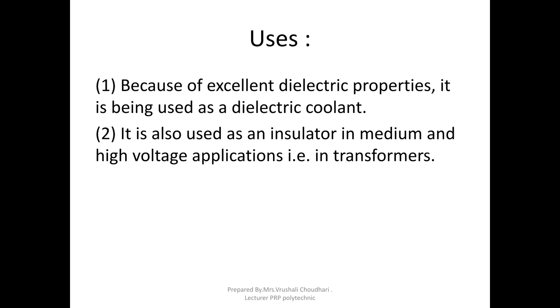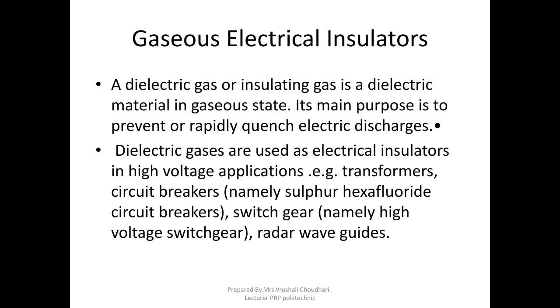Gaseous electrical insulator. Gas or air is a bad electrical conductor. Dry air is an insulator. But in the presence of moisture, the conductivity of air increases. This is also called ionization. Therefore, we cannot use normal air as an insulator in electrical appliances. A dielectric gas or insulating gas is a dielectric material in a gaseous state. The main purpose is to prevent electric discharge. Dielectric gases are used as electrical insulators in high voltage applications like transformers, circuit breakers, switch gears and radar wave guides.